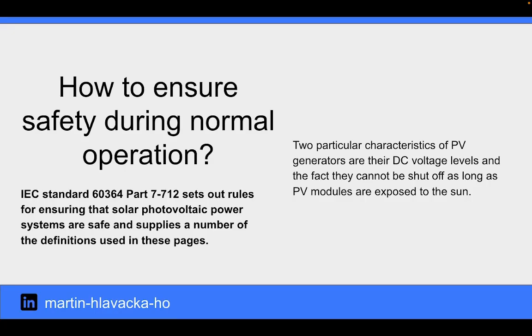So, how to ensure safety during normal operation? Two particular characteristics of PV generators are their DC voltage levels and the fact they cannot be shut off as long as PV modules are exposed to the sun.